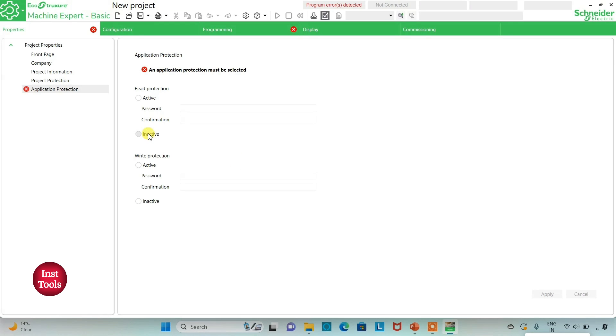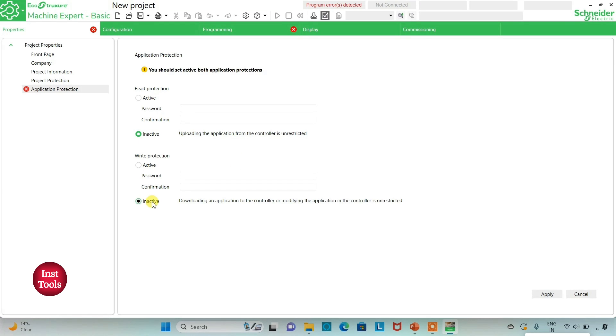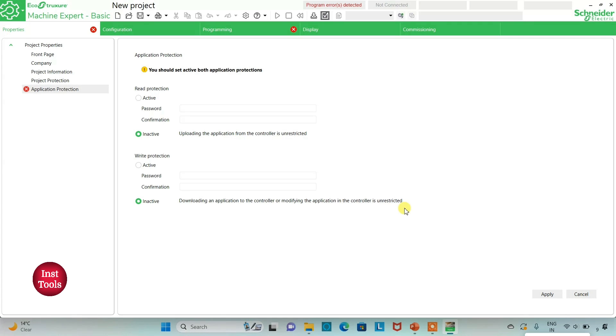I will keep read protection as inactive and write protection as inactive as well. That results in uploading the application from the controller being unrestricted, and downloading an application to the controller or modifying the application in the controller being unrestricted.